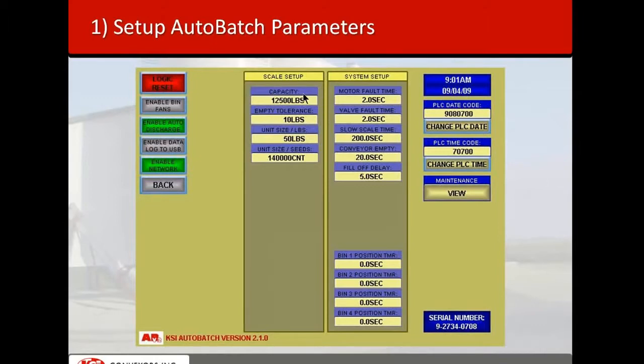The top field, capacity, is the scale capacity. It is currently set at 12,500 pounds. This is important. It tells the system how many pounds the scale can hold, so if there's an order greater than this amount, it's going to split that order into multiple batches.